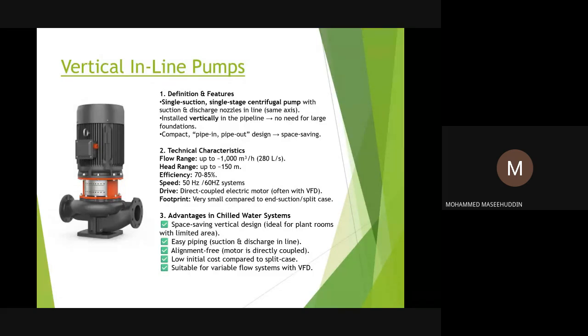I want to share one case study where we have supplied a pump with built-in VFD and display screen very recently, where we have found the pump to be very useful. It so happened that there was an installation done by our team for one chill water pump in a very big building here in Dubai. And the pump is meant for pumping about 70-75 liters per second of water to the chiller.